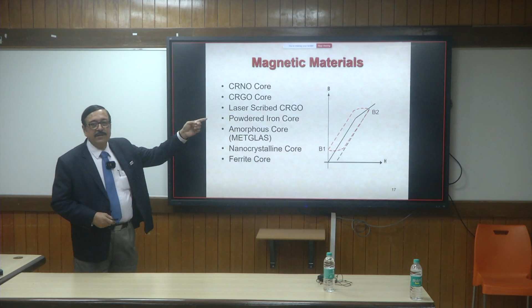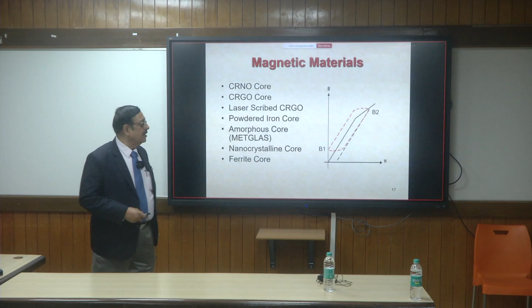Okay, so this second drawing is to inform you that when you have a unidirectional excitation, your flux density may have started from the main 0 point and goes up to the top point, but when it comes back, there will always be a residual value of flux density remaining, depending on the retentivity of the material. So the next time you start for unidirectional, it will be this, because you have only increased current H to a certain value and brought it back to 0. So in that process, flux density need not always come down to 0. It depends on the width of the hysteresis of this curve. So if it does not come down to 0, the next time you start is from this point. So the effective delta B variation that is permitted is B2 minus B1 and not the absolute value of B2. So in your calculation you have to be careful about this. Check out the retentivity, and if you are having a unidirectional flux operation, the deviation permitted delta B is B2 minus B1.